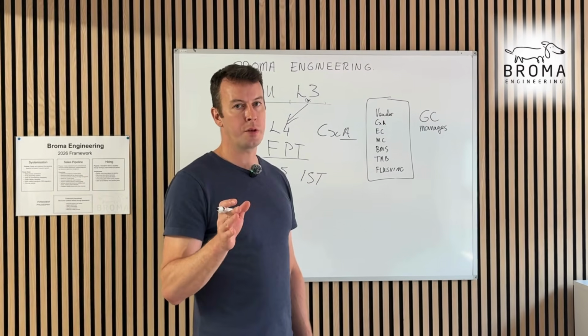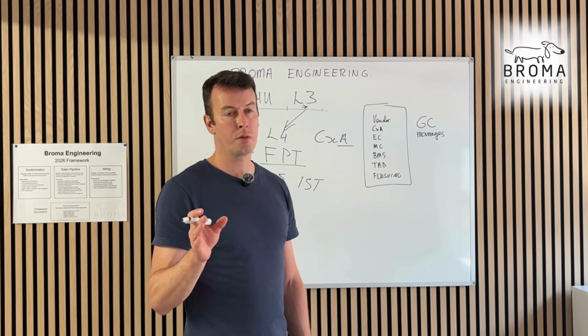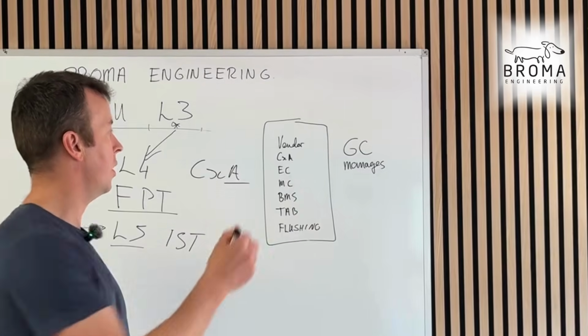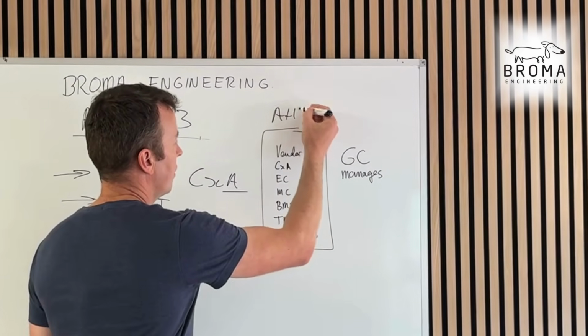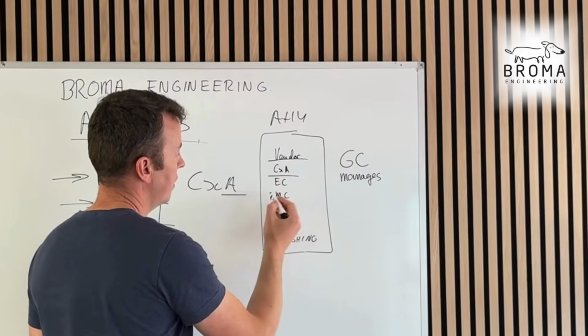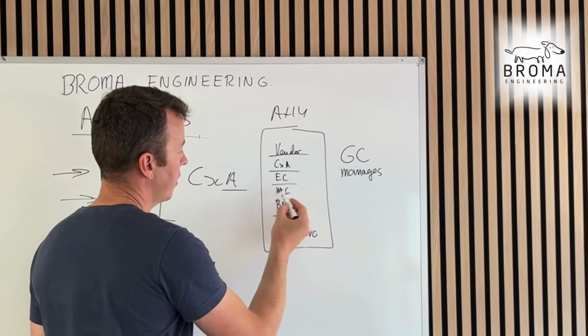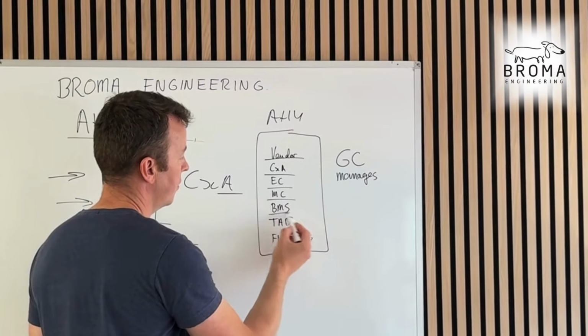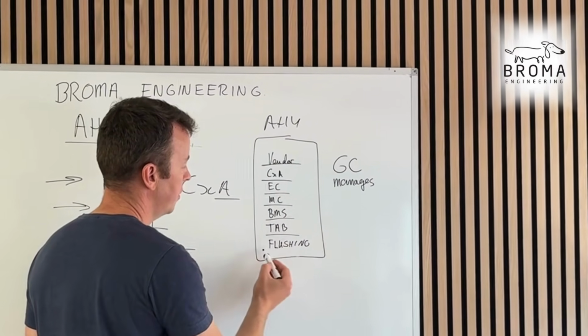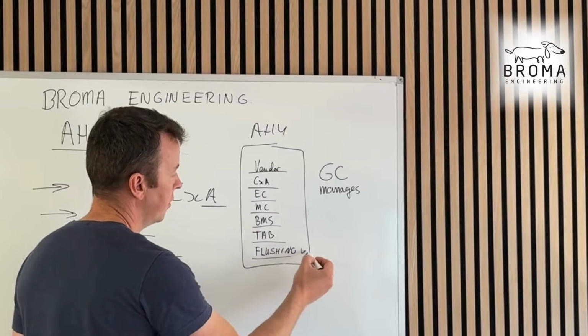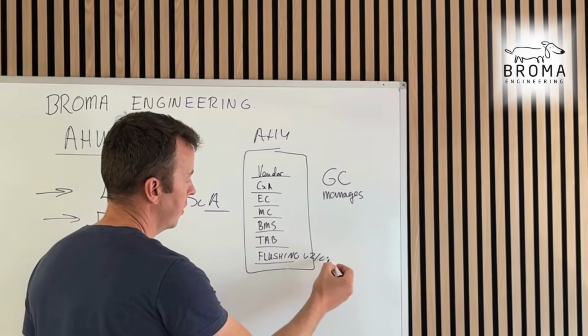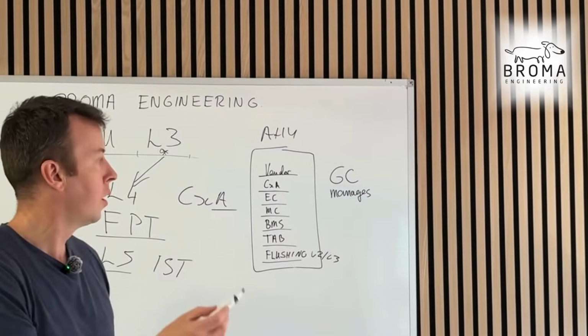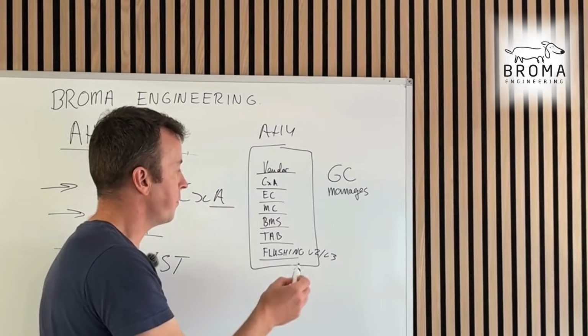So who needs to be there for commissioning level 3 in AHU? Obviously the vendor for the AHU, the CXA, the electrical contractor, the mechanical contractor, the BMS contractor, the TAB specialist, and the flushing specialist. That's level 2, we'll say, slash level 3 - that's a matter of opinion. But the rest is level 3.